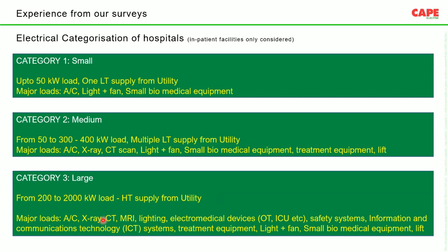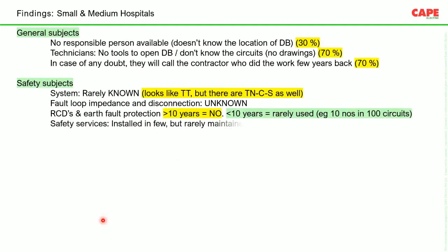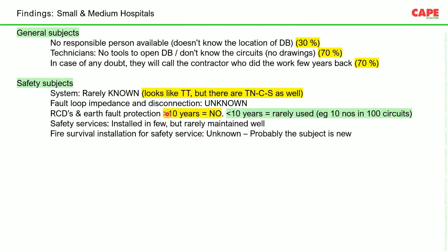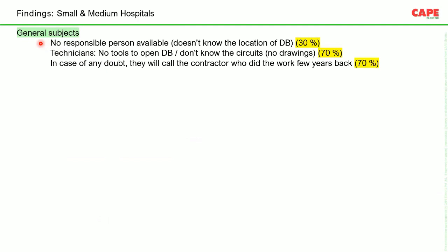Then we have the large category of hospitals, where HT supply, high voltage supply, is available, with proper transformers and all. We tried to make a survey, and the report of the survey, for example, in small hospitals, on general subjects: whether they have a responsible person, or whether people know where the electrical switchboard or the MCB distribution board is. If we ask the hospital people, yes, they know where the switches and sockets are, but most of them don't know where the MCB DB is placed. That means in case of any disconnection, it's a little bit of trouble.